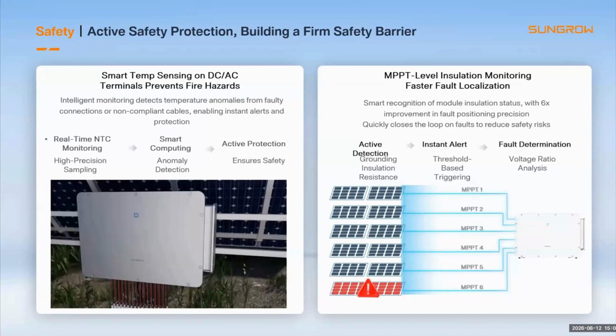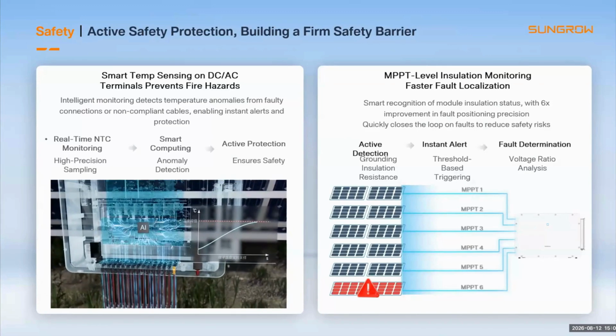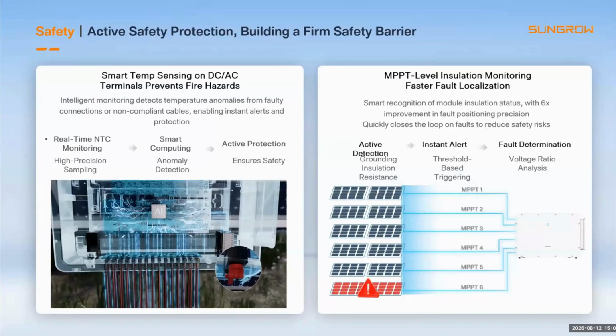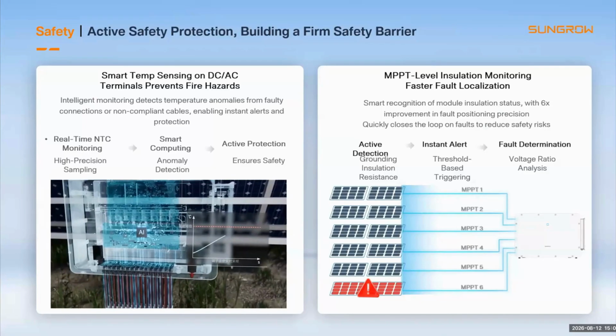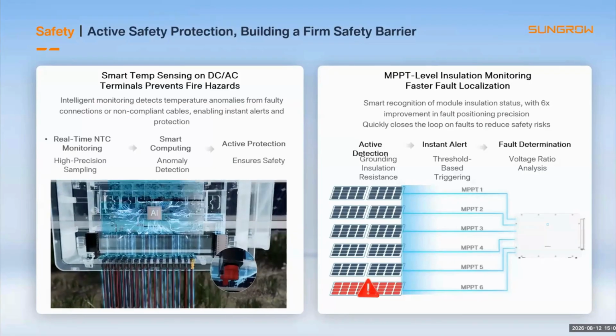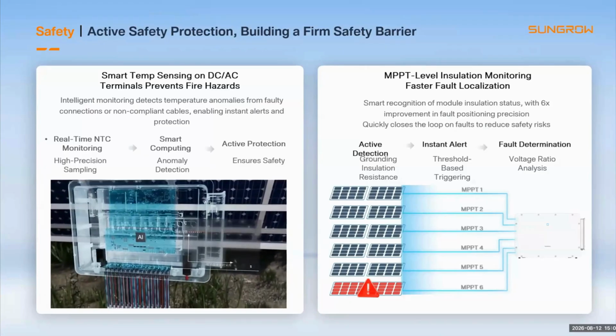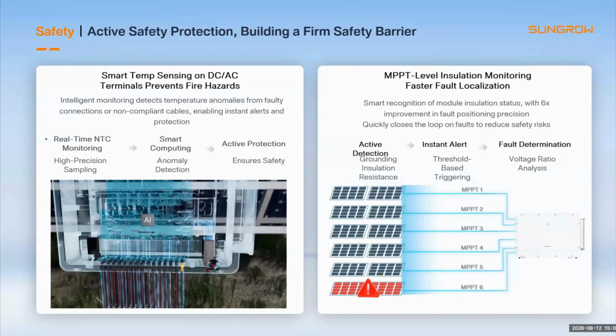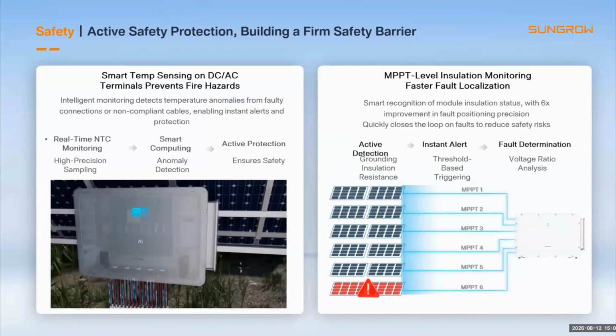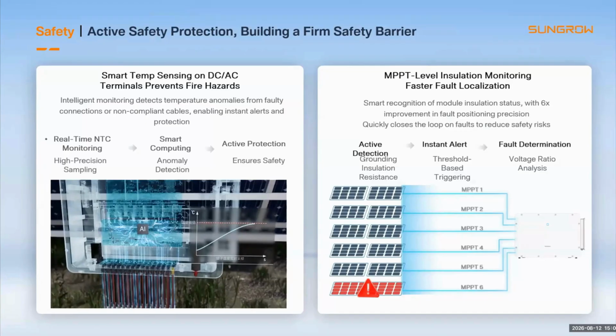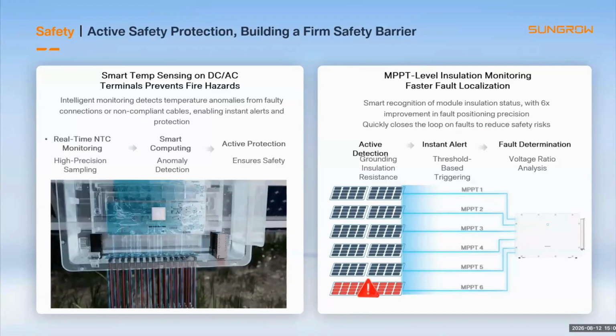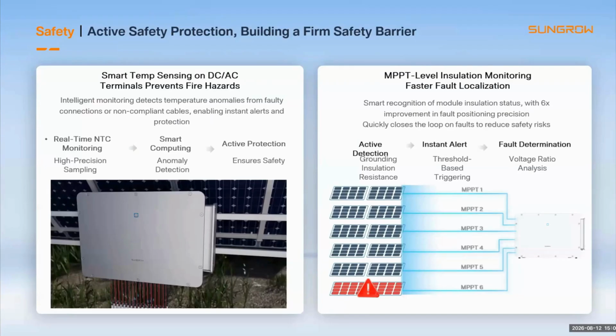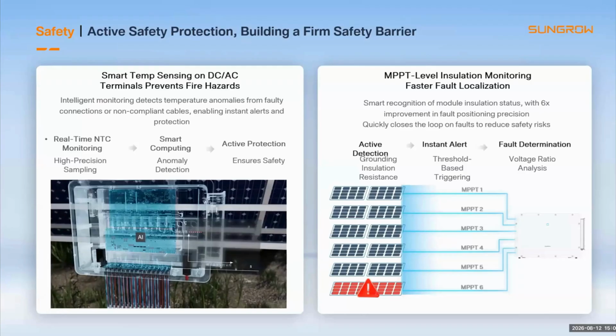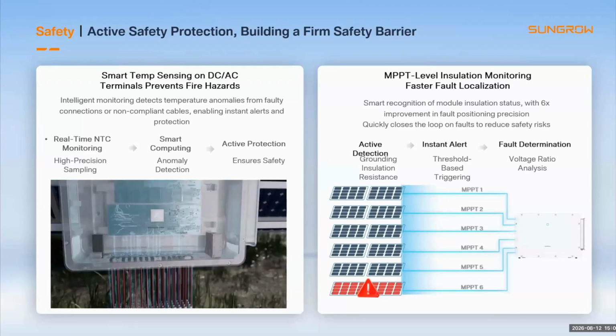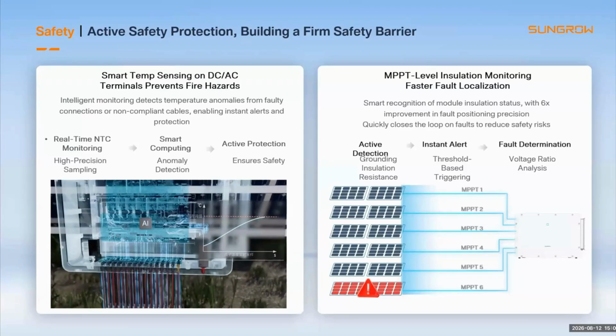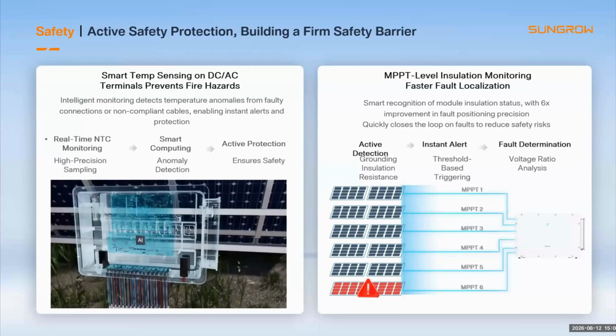Our SG510HX also includes real-time temperature sensing at DC and AC terminals. This helps identify abnormal heating caused by loose connections or installation issues before they develop into larger faults. MPPT-level insulation monitoring also improves fault localization precision. For O&M teams, faster detection means lower safety risk and shorter repair time.